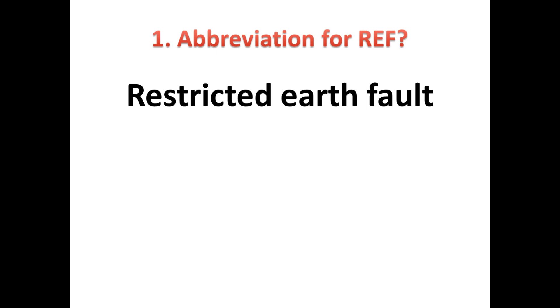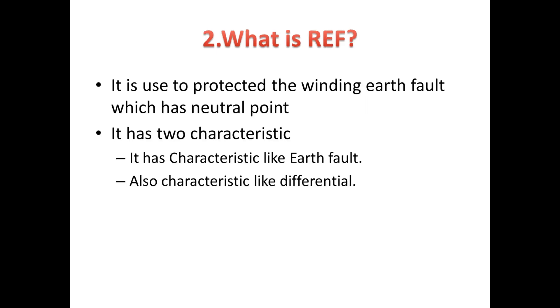Second question is: what is REF? It is used to protect the winding against earth fault, only for the winding which has a neutral point or is indirectly connected with the neutral point — commonly named as star-connected winding. This protection has two characteristics: first, it behaves like earth fault protection; second, it will also work like differential protection.